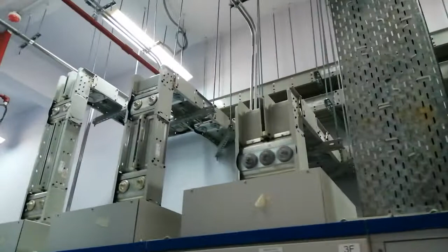From ATS to synchronization panel. See, this is the synchronization panel. And you see all connection by busway, in and out. So we have in only and out by cable from down. There is a down trench we have, and outgoing to the generator by cables, not by busway. Any busway is up to synchronization and ATS.